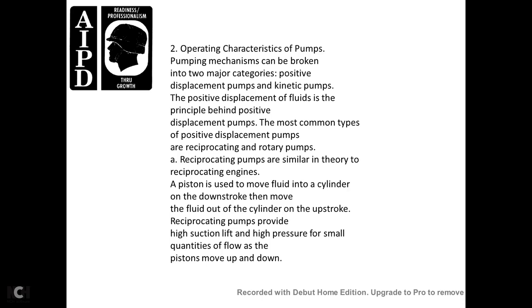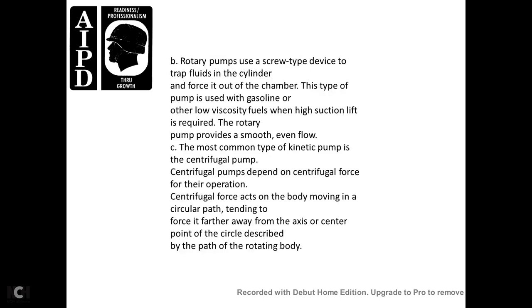Reciprocating pumps provide high suction lift and high pressure with pulsating flow as pistons move up and down. Rotary pumps use a screw-type device to trap fluid in a cylinder and force it out of the chamber. This type of pump is used with gasoline and other low-viscosity fuels where a high suction lift is required. The rotary pump provides smooth and even flow.